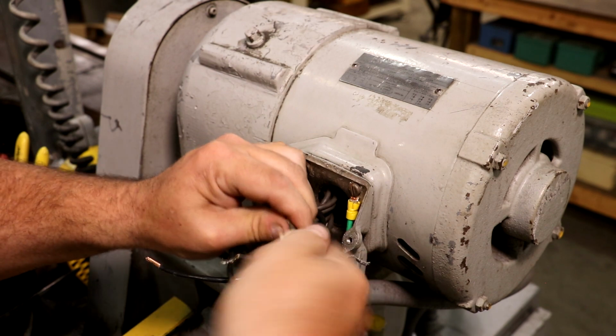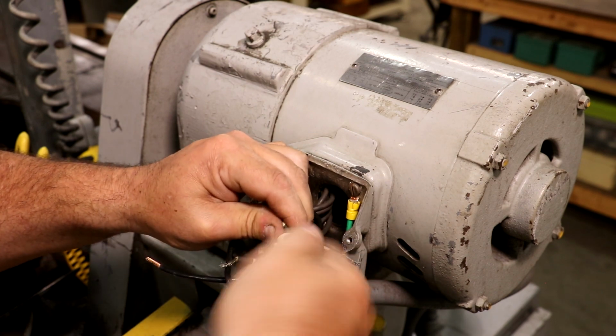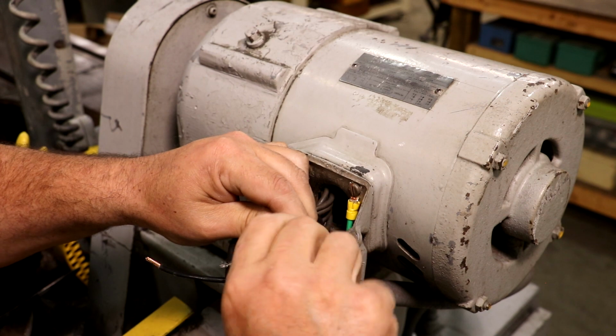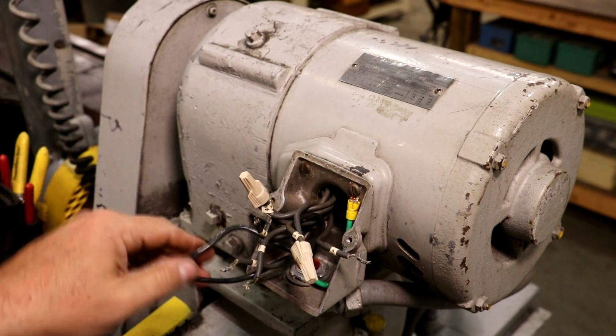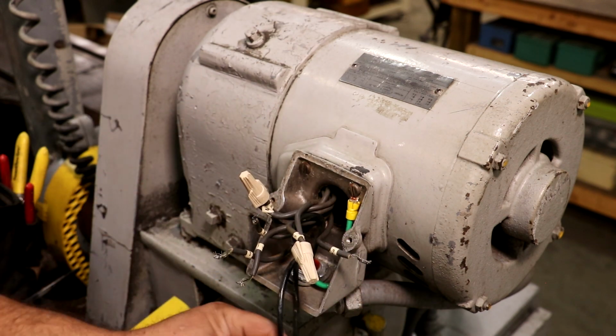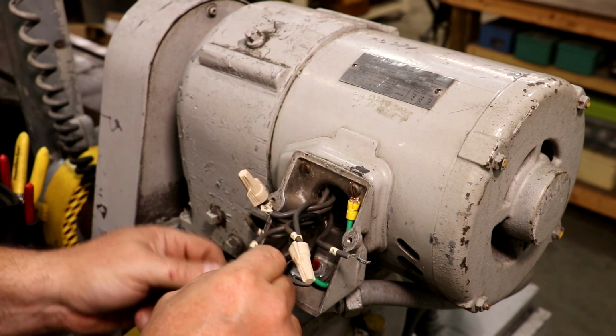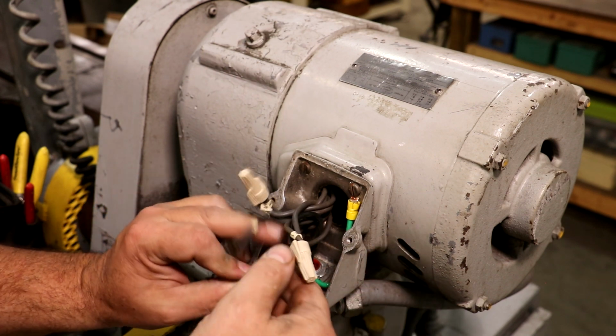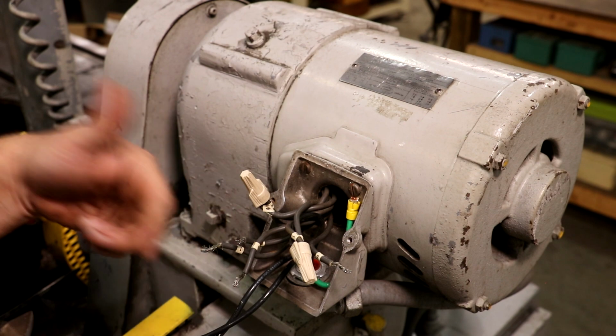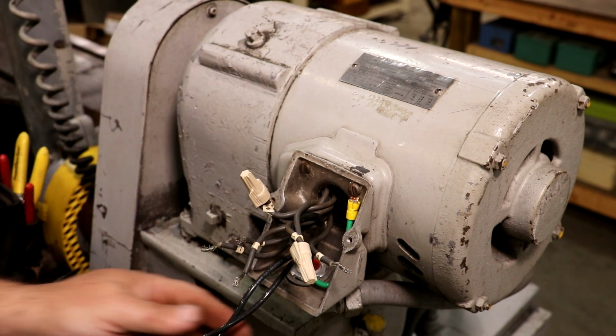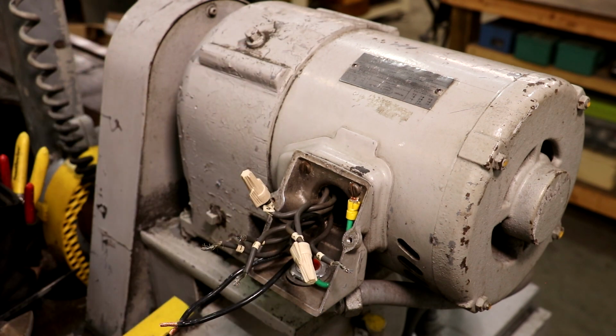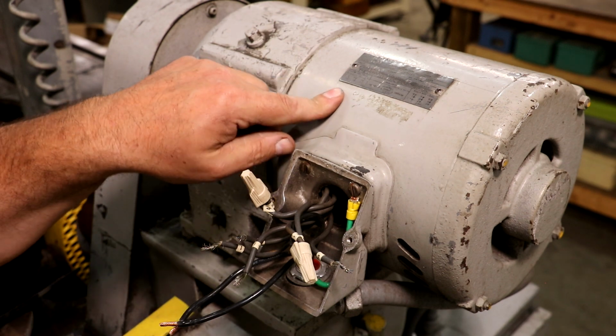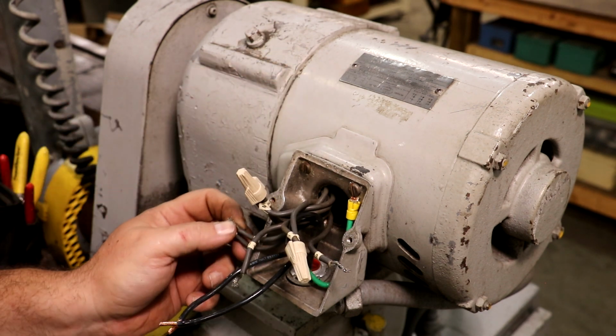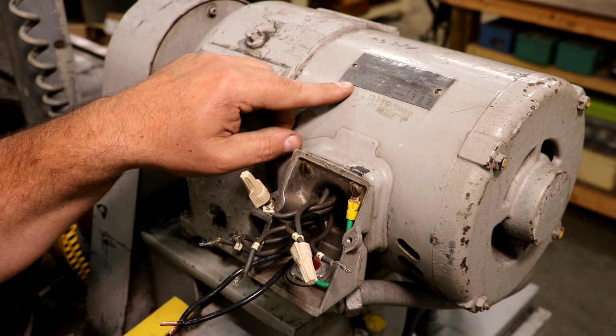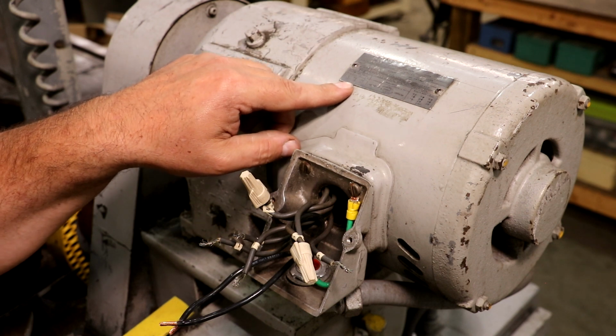Now, one thing I'll say is it doesn't really matter which one of your line feeds go to which one here. You've got 3 lines coming in. The motor may run in reverse whenever we first hook it up, but you can swap the rotational direction on a three-phase motor by swapping any two of your line feeds. You can just randomly do that, so we're not going to worry about it right now. We'll check the rotation, and if we need to, we'll swap one of the wires.